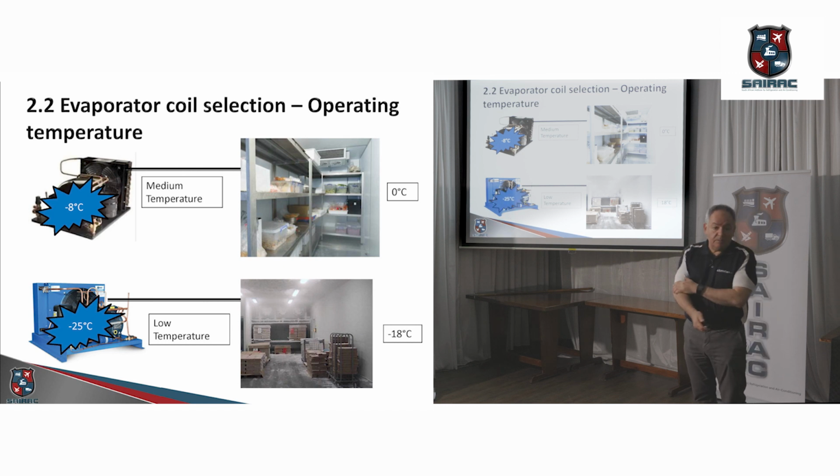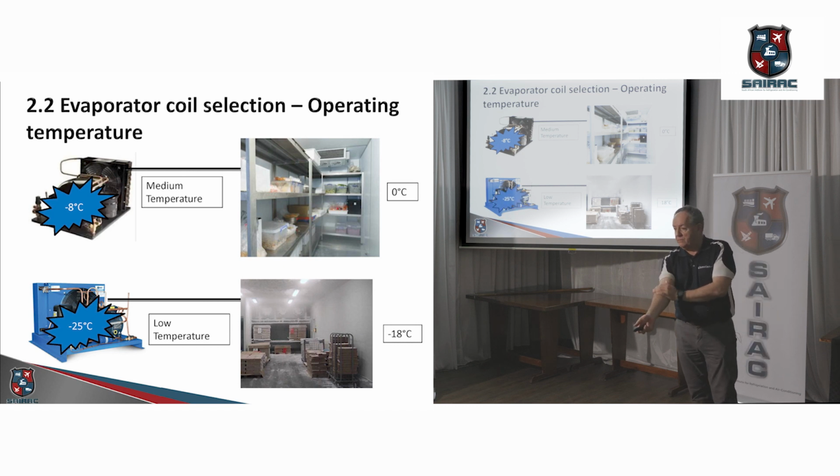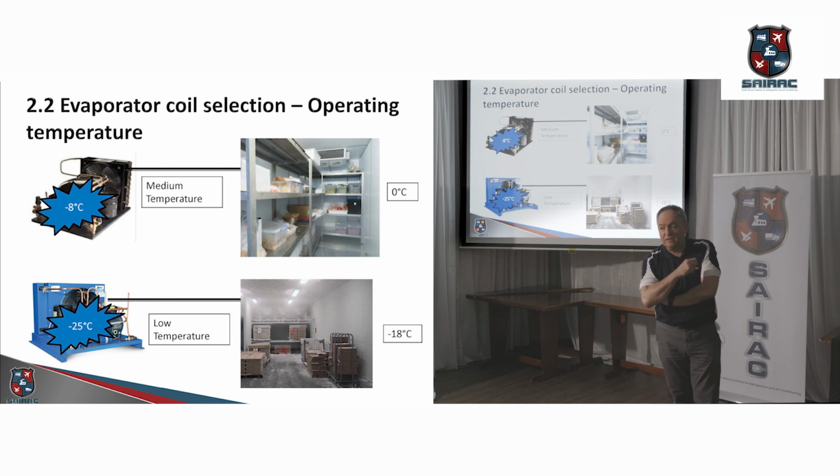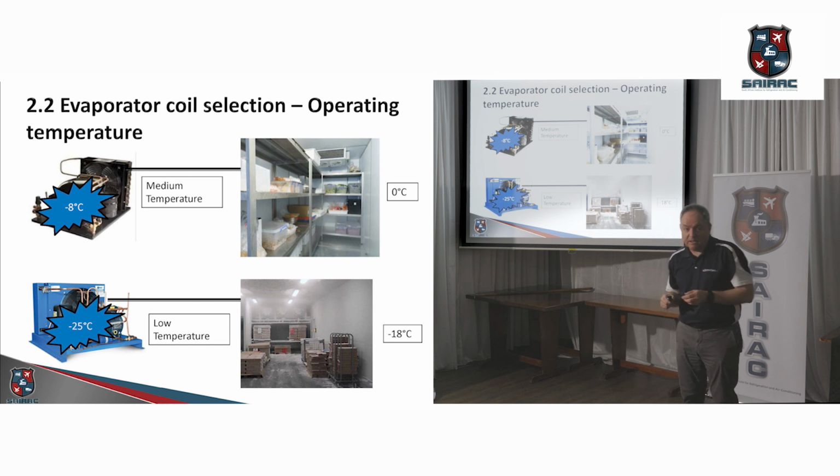So your suction temperature there is very commonly -25. You can certainly operate the compressor at -35, but obviously that consumes more electricity. So if you're generating it with diesel, then obviously it makes sense not to operate the compressor at a lower suction temperature if it's not required.